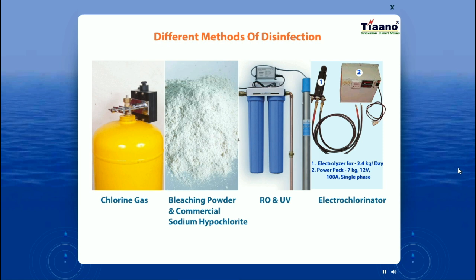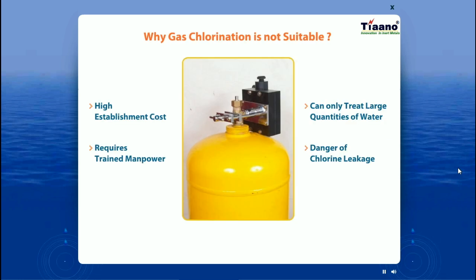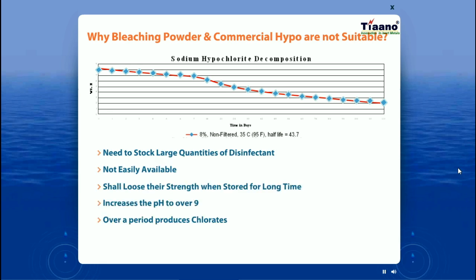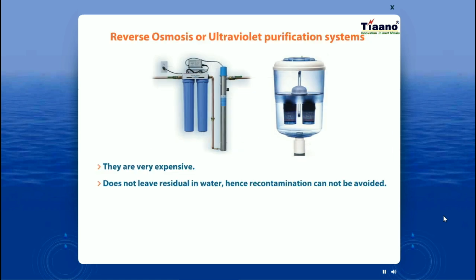Water can be disinfected using different technologies: chlorine gas, bleaching powder or commercial sodium hypochlorite, reverse osmosis, or ultraviolet radiation. Chlorine gas systems are costly, require highly trained manpower, and carry the danger of handling toxic gas. Bleaching powder and hypochlorite lose strength over time and raise water pH. RO and UV systems are expensive, suitable only for small quantities, and leave no residual disinfectant, so treated water can become recontaminated during storage.